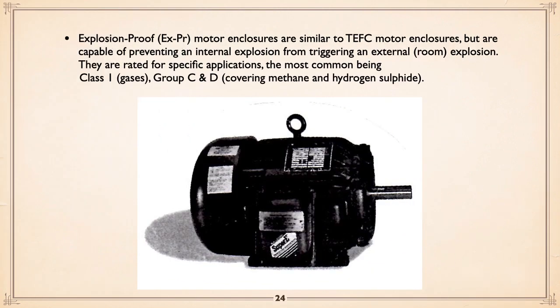Next enclosure, and the last one we're going to talk about, is explosion proof. Similar to TEFC, but again, they're built rugged so that if gases get into the motor somehow, even though they're enclosed, and a short or whatever triggers them and there's an explosion inside, it will not be conveyed into the room itself and blow up the room. And they're rated again for Class 1 gases, which is the most common. You can get them again for fibers and all that good stuff. And Group C and D cover methane and hydrogen. So explosion-proof atmospheres, Class 1 Group C and D, is the most common approach.